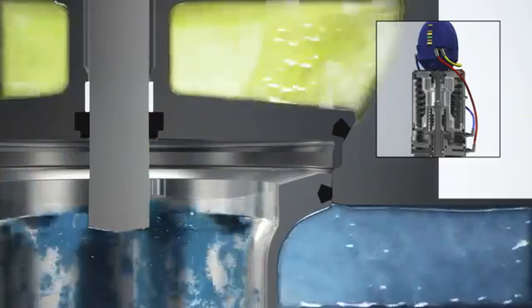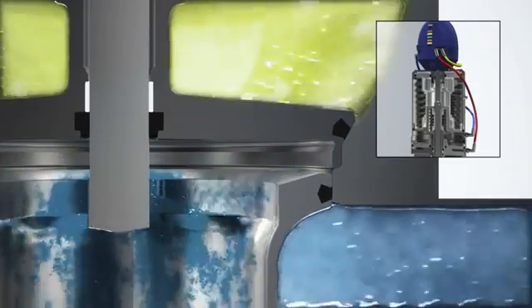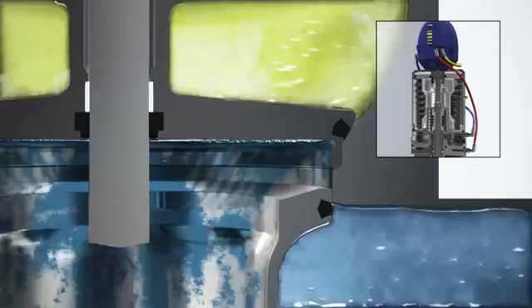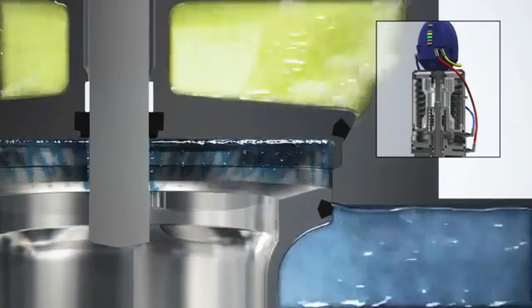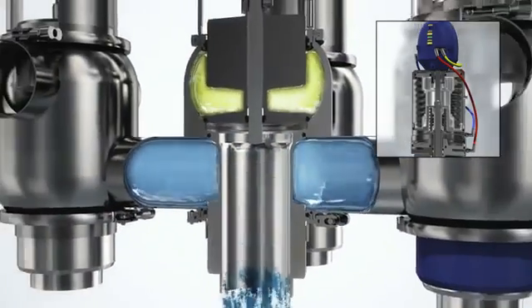This speeds up the cleaning process and uses minimal CIP fluid. It is important to adjust the duration of a seat lift or seat push operation to match the requirements of the process and product. If necessary, multiple seat lift operations can be performed.